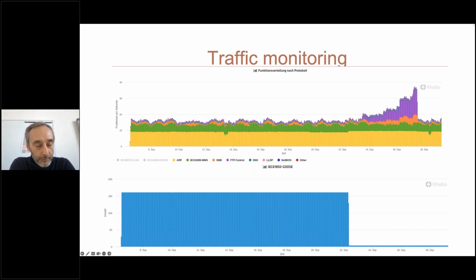The graph below shows a pretty radical issue, which is that at some point on September 22nd, the goose traffic stopped. In that case, I'd expect the process control system to detect this too. But in a less critical incident, we could see a pattern where the goose traffic degrades, in which case we could investigate before it actually stops on the system.